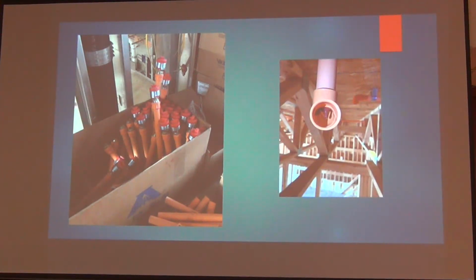So that's a lot to eat. Okay, so anyway, that's just part of the problem. The other part of the problem, see that little dangle right there? If they're gluing them with the sprinkler head in it, where's that glue go when they're pushing it together? It goes right into my sprinkler head and it keeps it from activating. If I see that, I make sure that I watch them throw all of those into the dumpster.